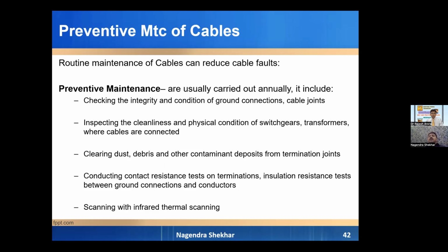So how to maintain these cables? Routine maintenance is usually annual. We have to check the integrity and condition of ground connections and cable joints. So basically, if it is possible to check underground joints or cable termination joints, we have to check. We can even thermoscan. Inspect the cleanliness and physical condition of switchgear and transformers where these cables are connected. So we have to open switchgears, check their connections, and ensure that there is no dust, no leakage current, no tracking. The sockets should be proper, and if required, we have to replace nut bolts or tighten the existing nut bolts properly. And we have to ensure the earth connections also.